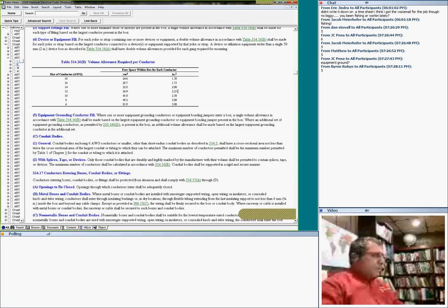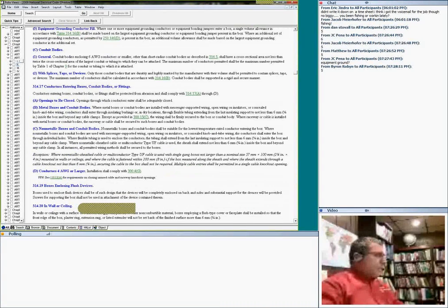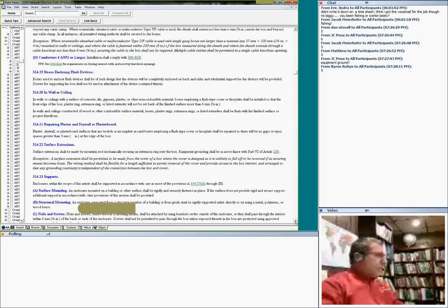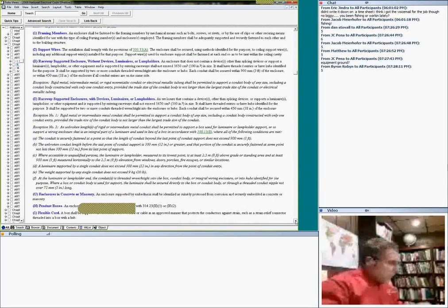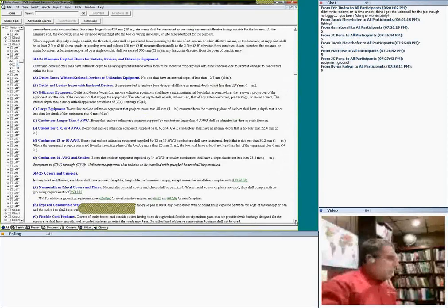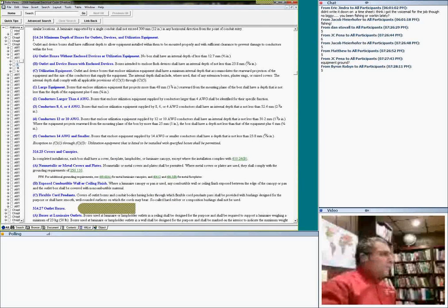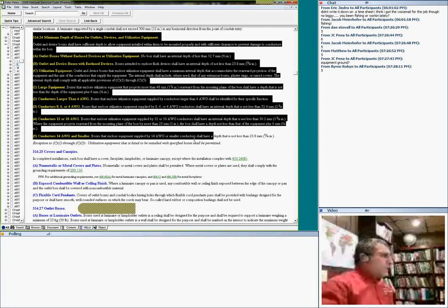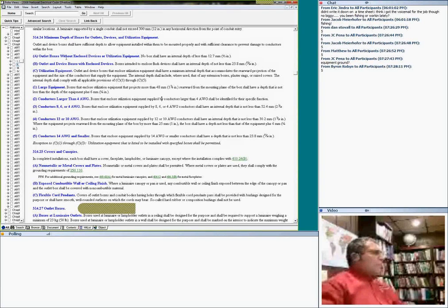they went and changed that one, in 2008 and still in 2009. They get into minimum depth, which is 314.24. 314.24, right in here. This article gives you the minimum depth all the way up to here. So if you're really interested, outlet boxes without enclosed devices or utilization equipment: no box shall have an internal depth less than half an inch. No minimum box is going to be less than half an inch.